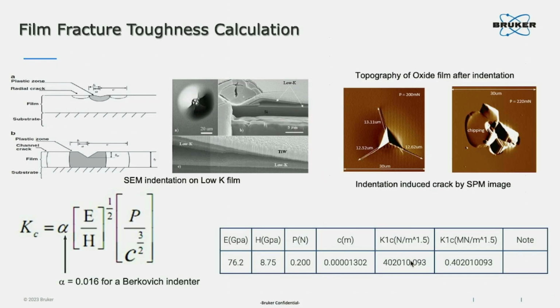We can measure the crack length by post SPM image. We can calculate the KC, the fracture toughness, by our machine. You see the formula is quite simple. Elastic modulus and hardness can be measured by nano indenter. Force is what we apply on the probe, and critical length can be measured by our SPM image. If you use Pico indenter, you can measure by the SEM, right? So everything can be measured by one machine. You get the KC, right?